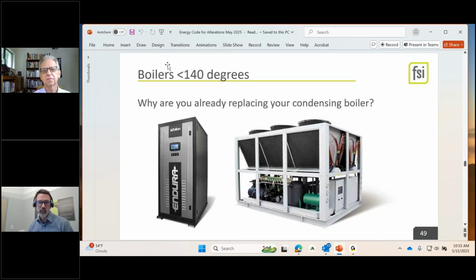All right. So if you're replacing your condensing boiler and you're already on a less than 140 degree loop, sometimes a 120 degree loop, you might be able to get there now without putting in a backup boiler or without using your 50% allowance of gas, just because of where chillers have come in the last 2 years.